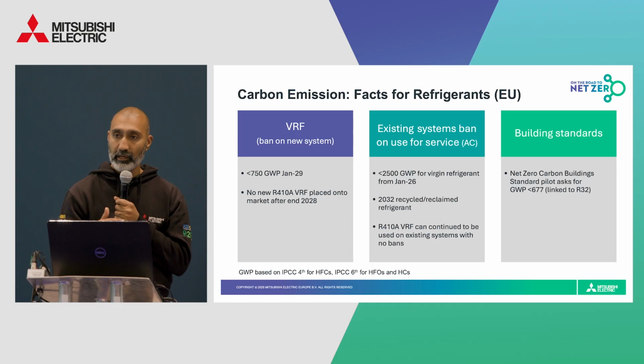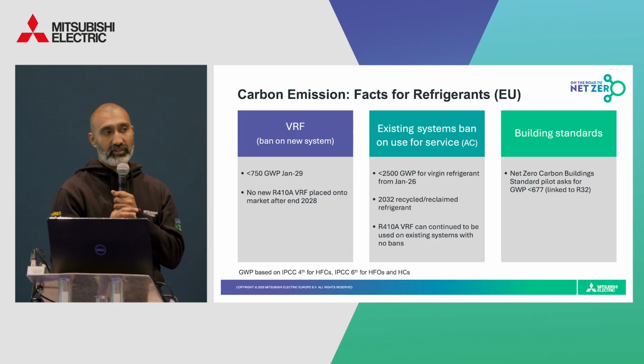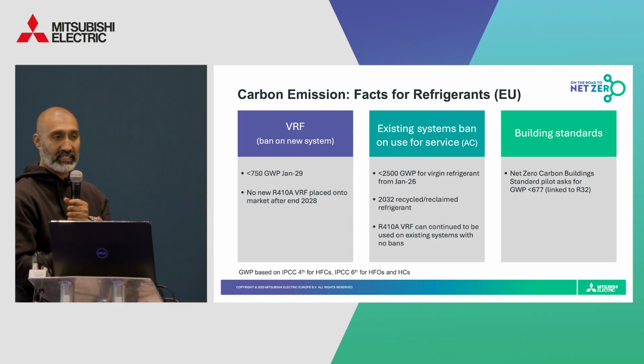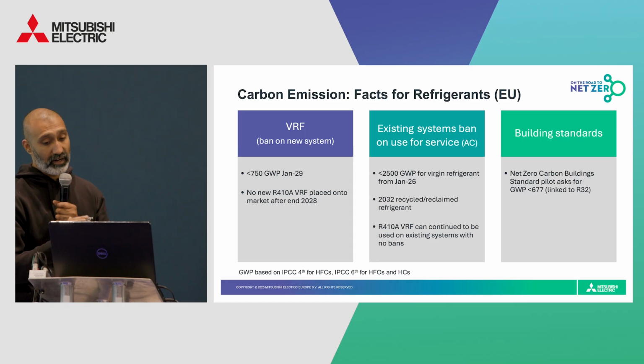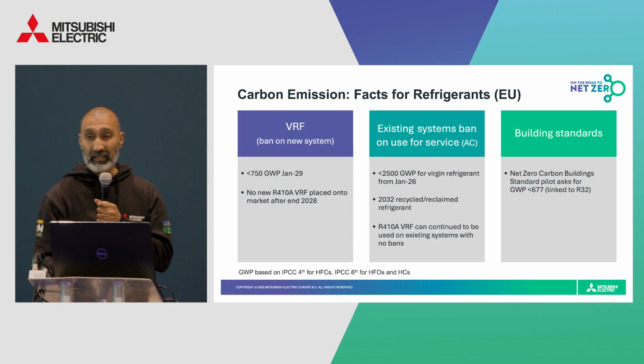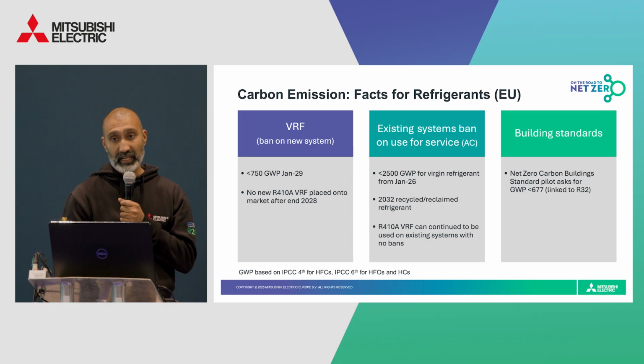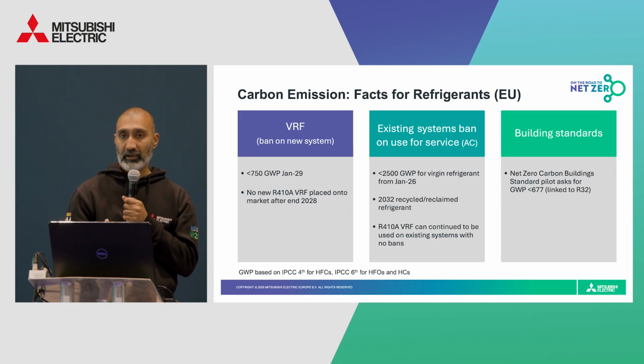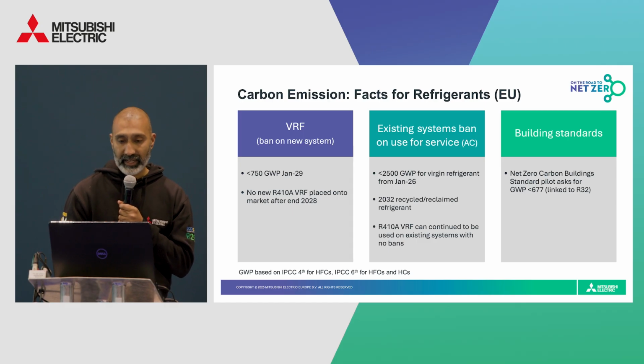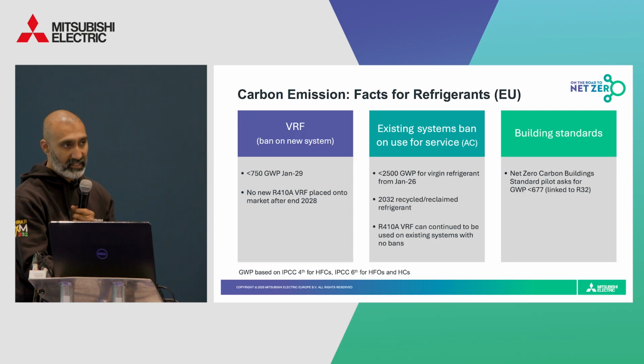greater than or equal to 12 kilowatts has been set at 750 from the 1st of Jan 2029, and then it's been set at 150 from the 1st of Jan 2033. And this basically means that in 2029, no new R410A VRF systems will be allowed on the market, thus requiring alternative refrigerants with lower GWPs.